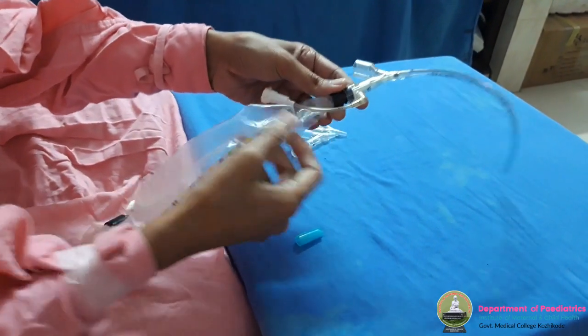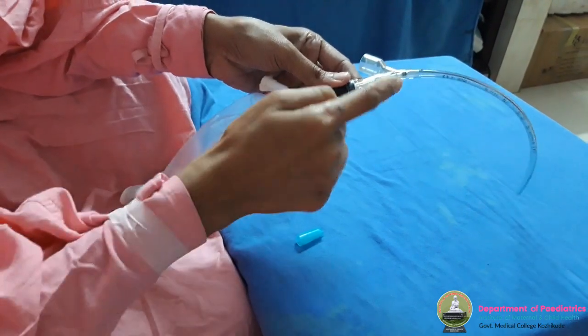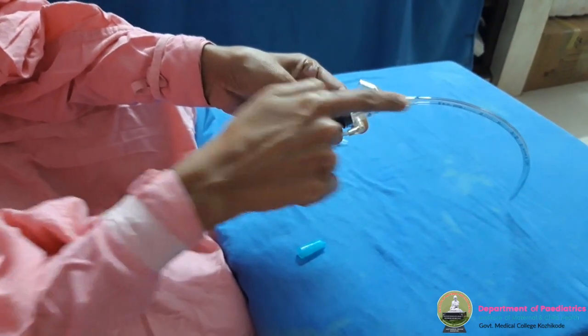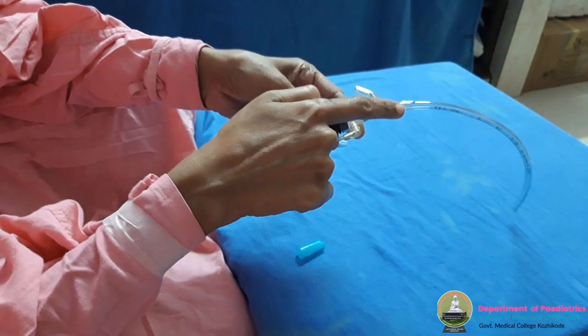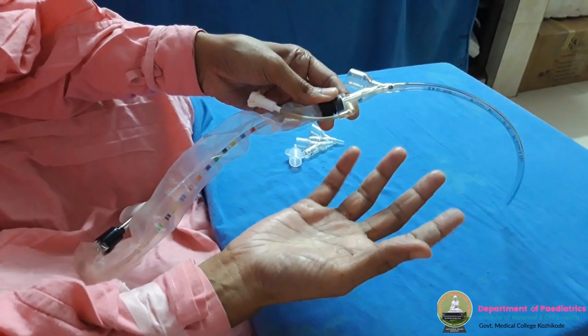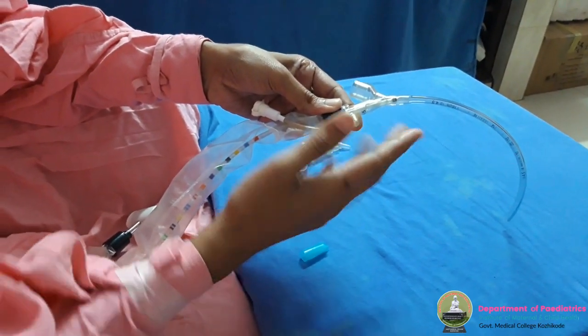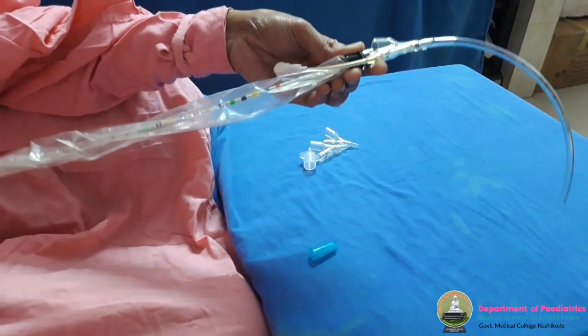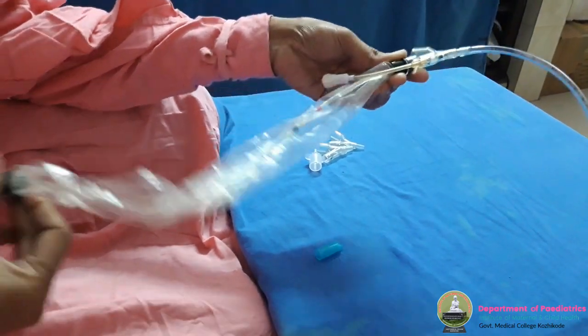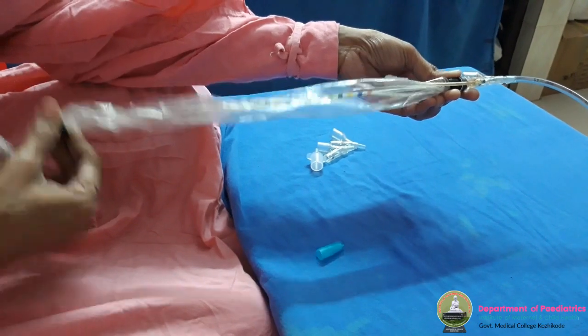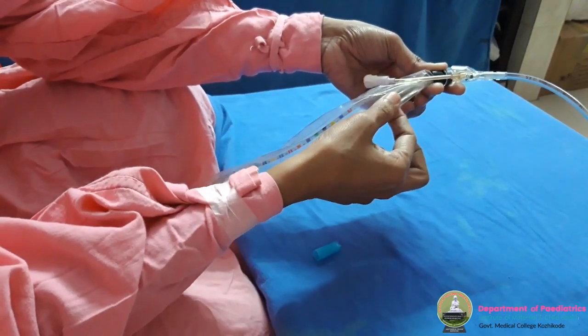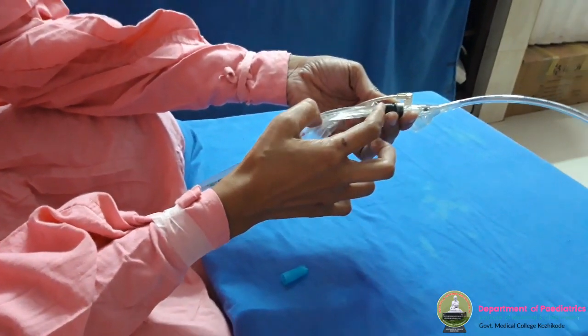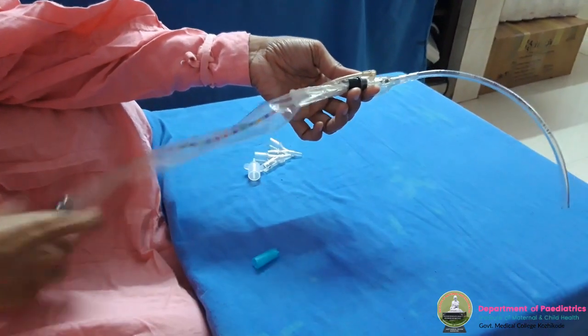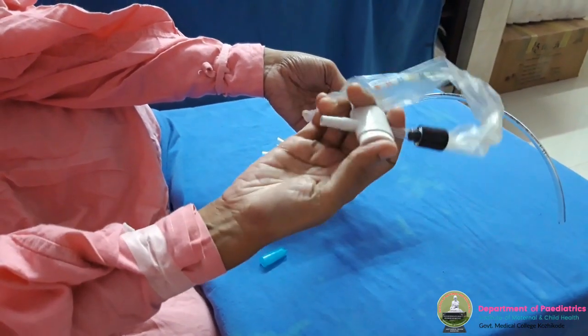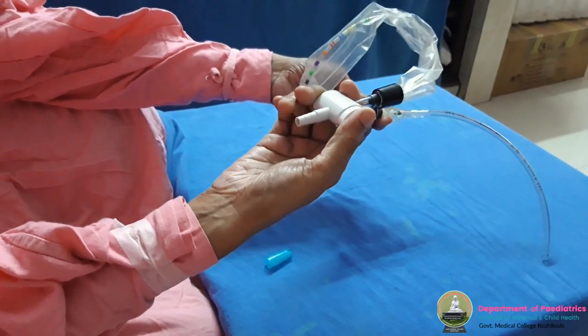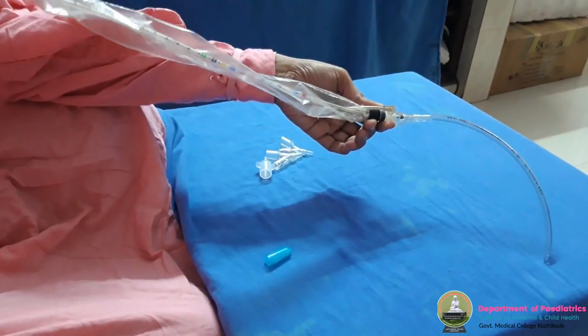What is the problem if it is less pulled? This will obstruct the gas flow. It is a great obstruction to the gas flow. We will get a high PIP alarm and the patient will become hypoxic. So that is to be ensured. Another point is that when you are pulling it back, you should not pull by holding the polythene cover. It will rupture here. So always hold on the white last tip and press it and then pull.